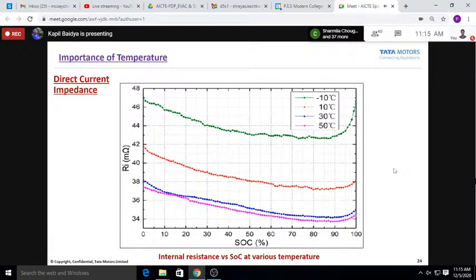This is very interesting. This plot shows the state of charge from 0 to 100%, and the other plot shows the direct current impedance. If the cell is maintained at minus 10 degrees centigrade, very low temperature, then your impedance is increasing. When the charge is lesser, from 0 to 10%, the impedance is more compared to 50 to 80% SOC, where the impedance is quite flat and constant. Again, when the charge is high, the battery is full at 100%, the impedance suddenly increases from 90 to 100%. So that is the trend at all the different temperatures.